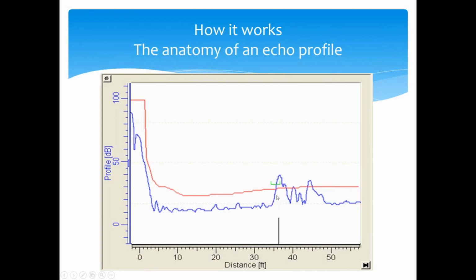So as you have things like foam, for example, as Sean asked about, the foam in the tank is going to decrease this signal. So if the size of this amplitude comes down, that red line will come down with it. So we still continue to measure level for you, and we don't go into echo loss. That's the whole purpose behind having this dynamic threshold or the dynamic red line.